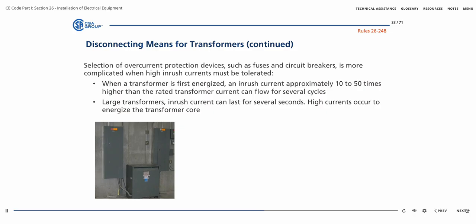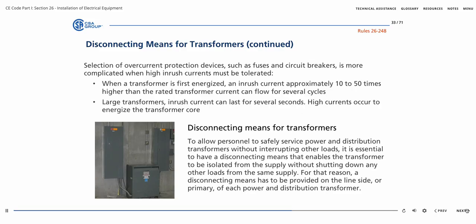The high currents occur to energize the transformer core. The steady state magnetizing current of a transformer is very low, but the momentary current, when it is first energized, can be quite high.